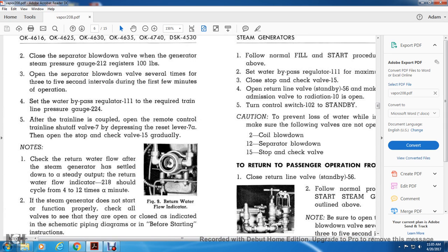2. Close the separator blowdown valve with the generator steam pressure gauge 212 registering at 100 pounds. Open the separator blowdown valve several times at 3 to 5 second intervals during the first few minutes of the operation. Set the water bypass regulator 111 to the required train line pressure gauge 224.